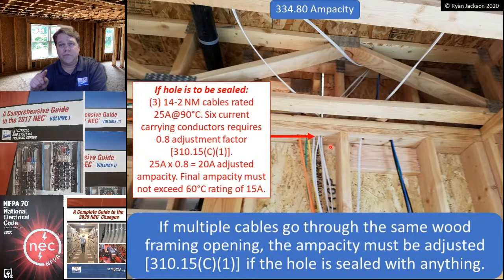That's six current carrying conductors. You always count the neutral on a two-wire circuit. Don't have to count it usually if it's a shared neutral. Six current carrying conductors, I go to table 310.15(C)(1), and I find out that six current carrying conductors is a 0.8 adjustment factor. Take my 90 degree ampacity, multiply that by 0.8, and that is your final adjusted ampacity. And as long as that ampacity works for the circuit, then you're okay. So three 14-2s, 25 amps times 0.8 equals 20 amps. Can I put a 20 amp wire on a 15 amp breaker like I was going to anyway? Of course. So you're good to go.